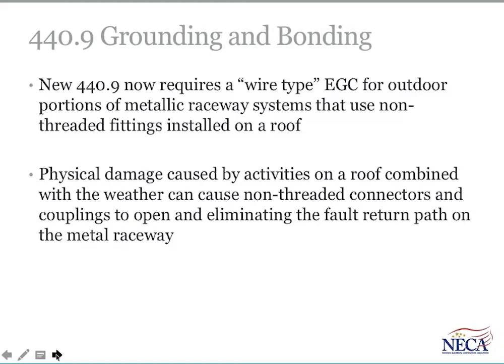This is a significant change in Article 440. Of course, Article 440 deals with air conditioning and refrigeration equipment. In the grounding and bonding area, a new Section 9 has been added to the article, and it requires a wire-type equipment grounding conductor for outdoor portions of metallic raceway systems that utilize non-threaded fittings installed on a roof.